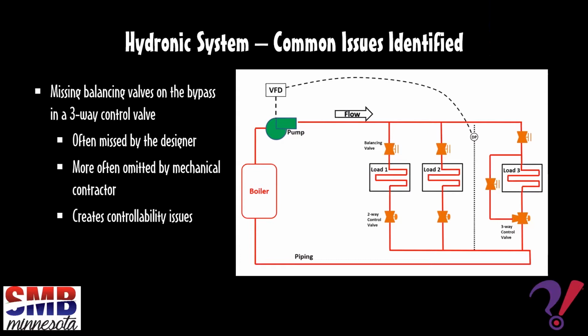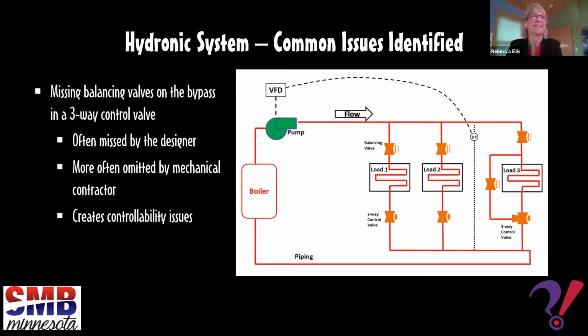So next question, one attendee asked, is the bypass balancing valve balanced for the same water flow as the balancing valve for the corresponding load? Yeah, I can answer that. Okay, so on a system like this one right here, it does not necessarily, if you went full flow to the coil, you're going to have a certain pressure drop across the coil.